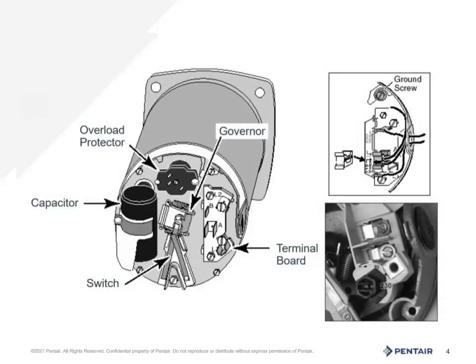This is a line drawing of the same components, including the thermal overload, capacitor, switch, governor, and the terminal board. The terminal board is where the voltage comes in at line 1 and line 2. There are a variety of boards shown here depicting the different methods of changing voltage over the years. The most current is the black and white picture in the lower right hand side. Note all our motors go out wired 230 volt unless otherwise noted on the motor or in the manual. This is to prevent accidental damage to the motor should the wrong voltage be applied.